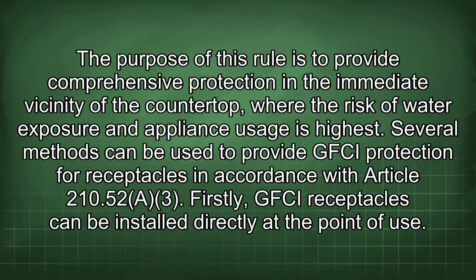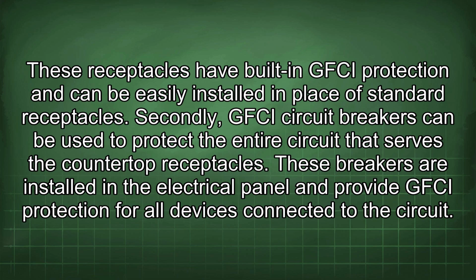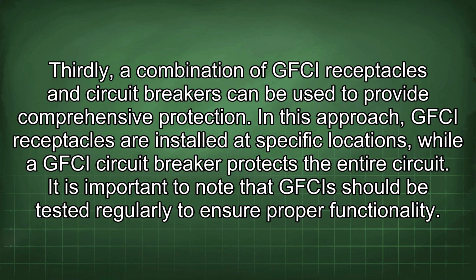Several methods can be used to provide GFCI protection for receptacles in accordance with Article 210.52(A)(3). Firstly, GFCI receptacles can be installed directly at the point of use. These receptacles have built-in GFCI protection and can be easily installed in place of standard receptacles. Secondly, GFCI circuit breakers can be used to protect the entire circuit that serves the countertop receptacles. These breakers are installed in the electrical panel and provide GFCI protection for all devices connected to the circuit. Thirdly, a combination of GFCI receptacles and circuit breakers can be used to provide comprehensive protection. In this approach, GFCI receptacles are installed at specific locations, while a GFCI circuit breaker protects the entire circuit.